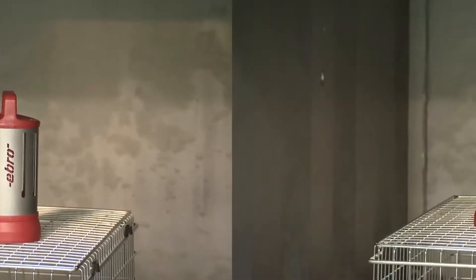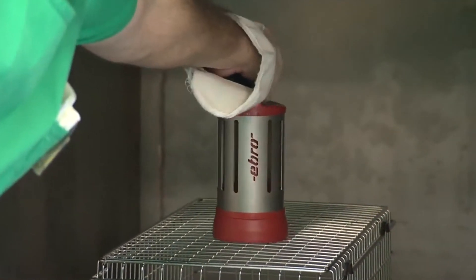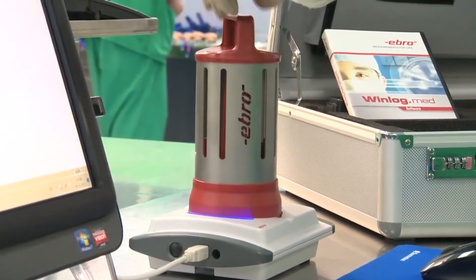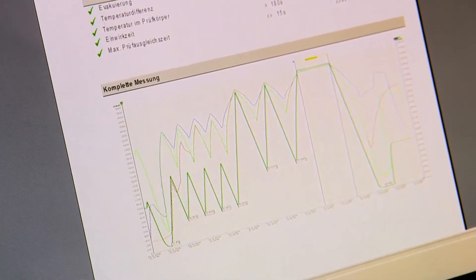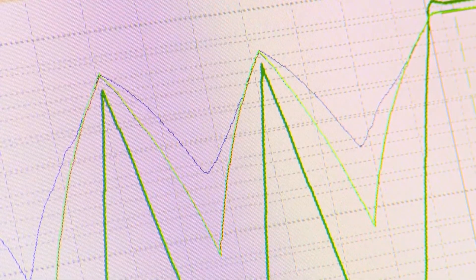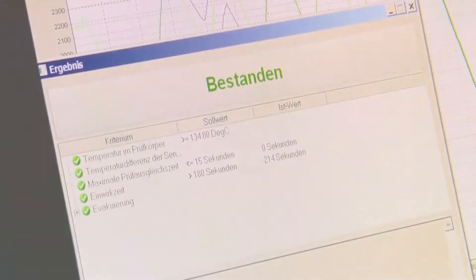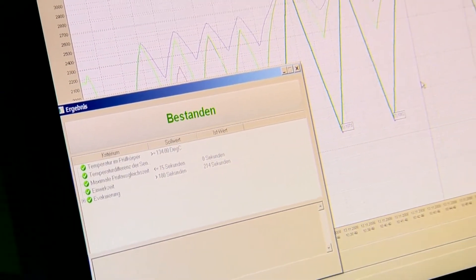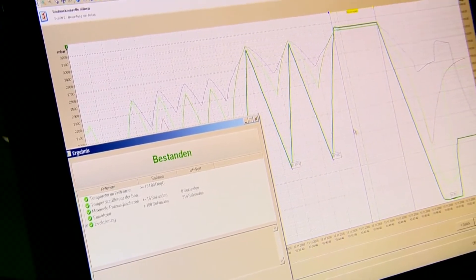The vacuum and sterilization phase of the sterilizer is monitored in its entirety. In a graphic representation, the program identifies both a defect-free sterilization cycle as well as one exhibiting defects. In the event of cycles exhibiting defects, the deviations are documented and possible causes of the defects indicated.